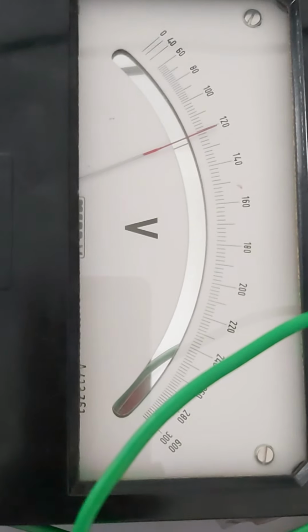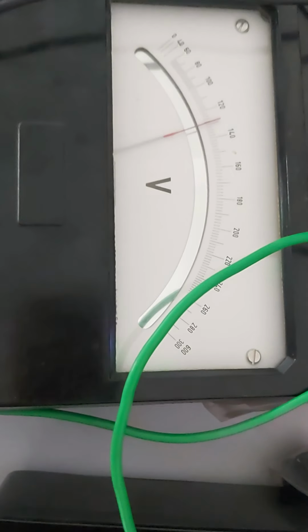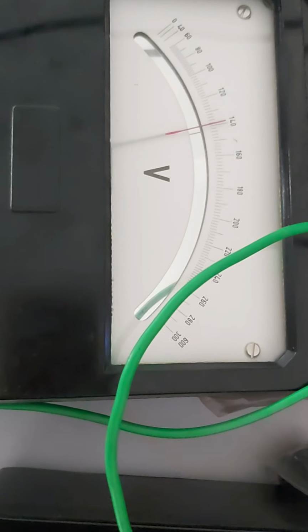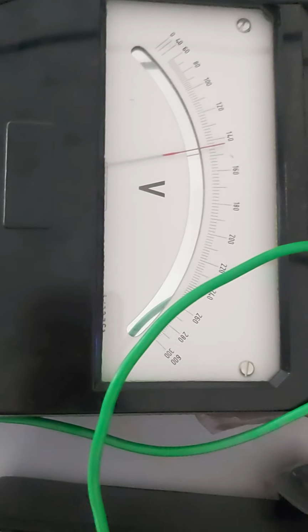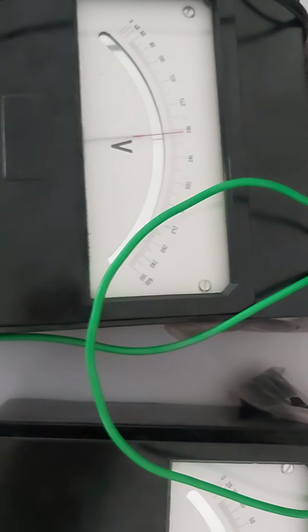Next, again I am increasing the voltage up to 120 volts, and again by increasing the voltage step by step you can note down the readings up to rated voltage. The rated voltage of the single phase transformer is 220 volts. Same, gradually 160. At 160 again you note down the values. At 180 again you note down the values of VT, VM and V0. So you can apply the voltage up to the rated voltage on the single phase transformer.